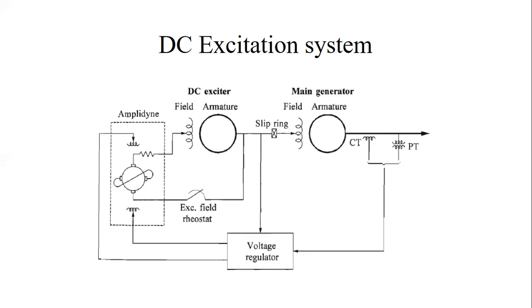As developments have come into the picture, DC excitation systems have been replaced by AC or static excitation systems. In some cases the voltage regulators alone have been replaced by modern solid-state electronic regulators, but many DC excitation systems are still in service and still require modeling in stability studies. The figure shows the schematic of a simplified representation of a typical DC excitation system with an Amplidyne voltage regulator. It consists of a DC commutator exciter which supplies direct current to the main generator field through slip rings.